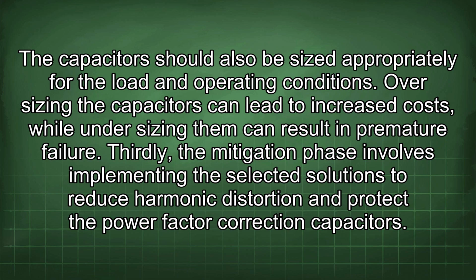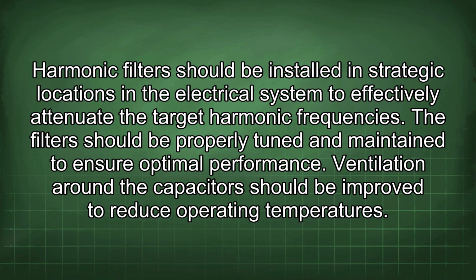Thirdly, the mitigation phase involves implementing the selected solutions to reduce harmonic distortion and protect the power factor correction capacitors. Harmonic filters should be installed in strategic locations in the electrical system to effectively attenuate the target harmonic frequencies. The filter should be properly tuned and maintained to ensure optimal performance.